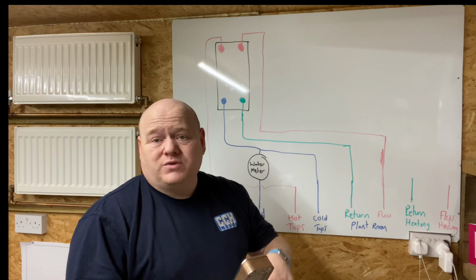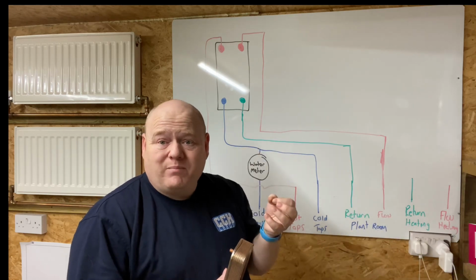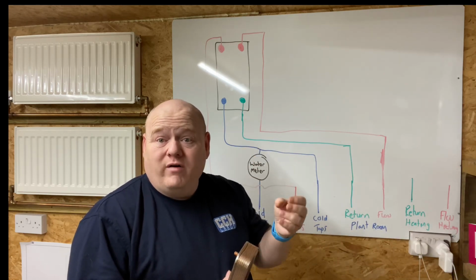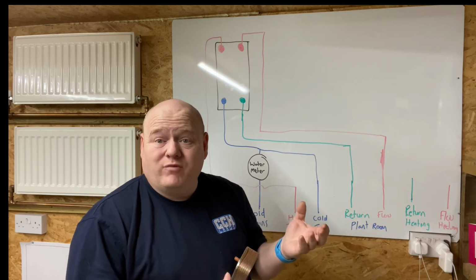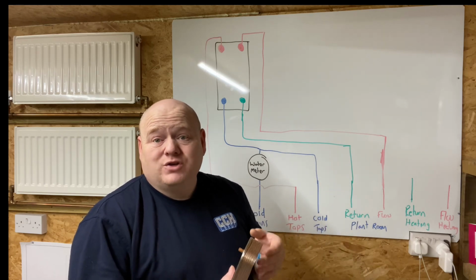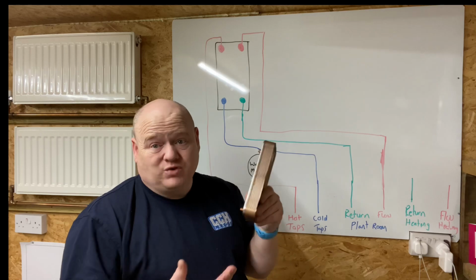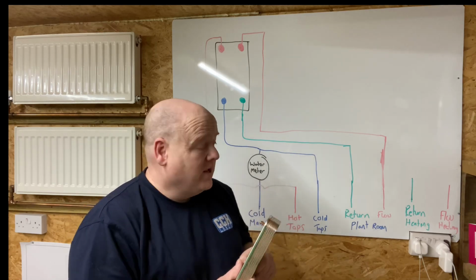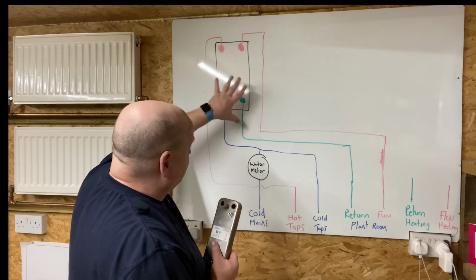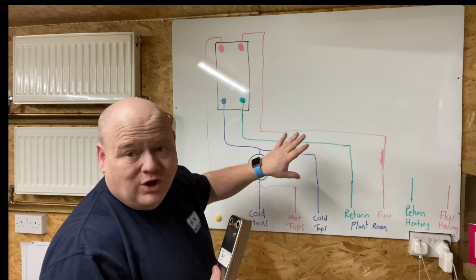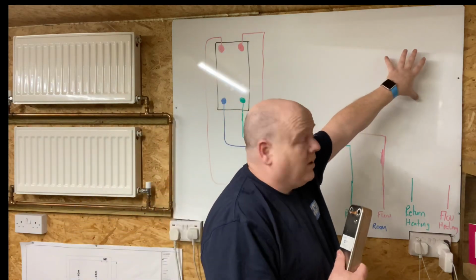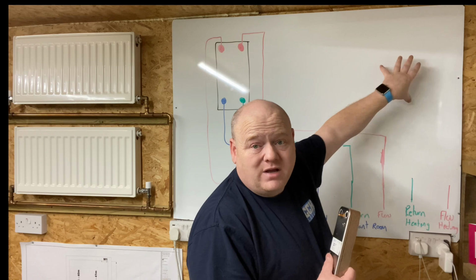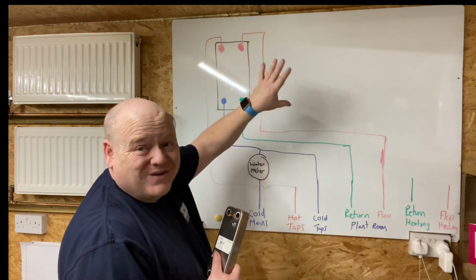But what you don't want to do is be opening your hot tap and getting water from the central heating or from the plant room coming out of your tap. So that's why, or that's one of the reasons, you would have a plate on this. So that doesn't mix. So now what we'll do, we'll add this other plate heat exchanger up here, and I'll try and explain that one in detail if I can.